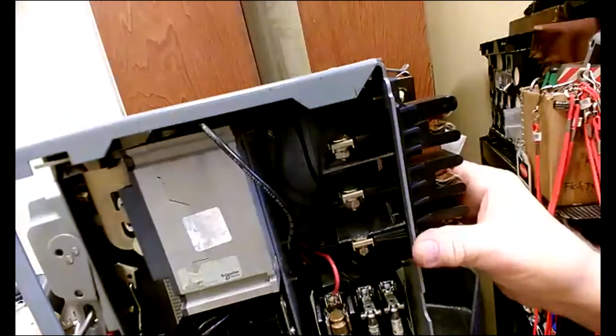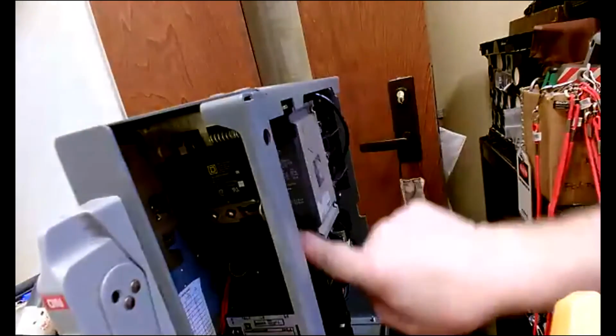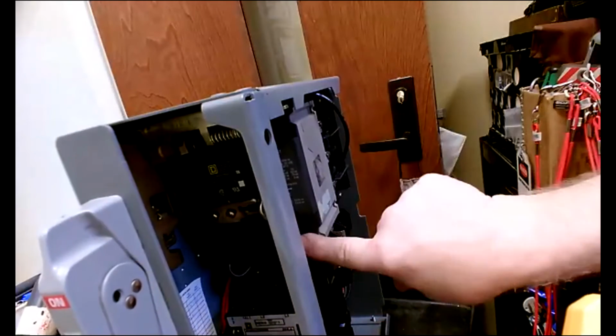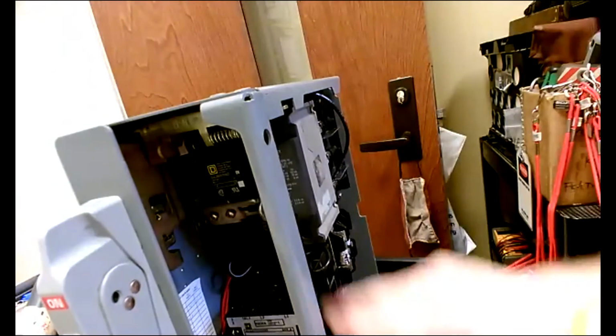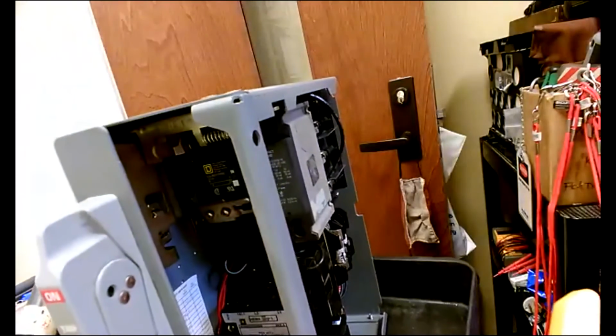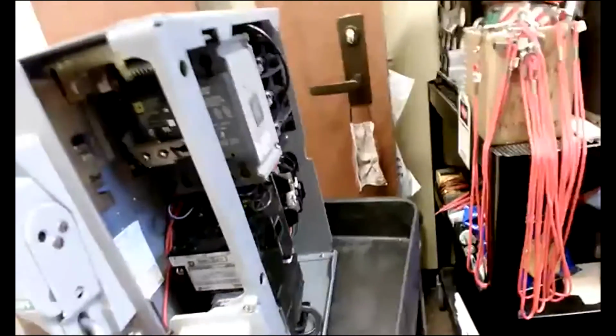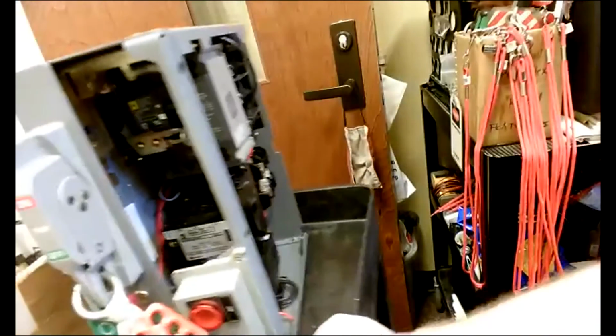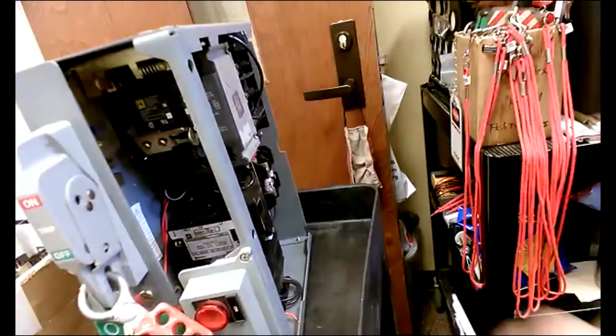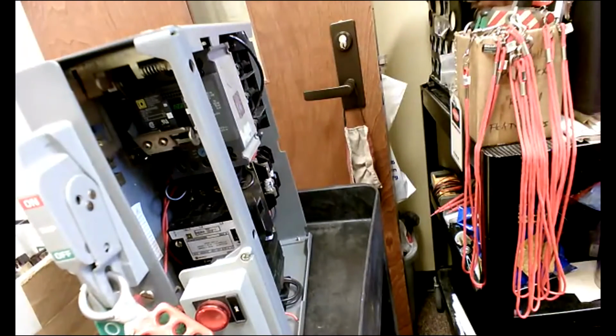Now we know that the main power feeds in from the back bus bars here, from here where it plugs into a wall structure through the breaker panel, so to the breaker. So if the breaker's dead, we know the rest of it's dead. Everything else is downstream, here in this motor control, okay? So we saw that was dead, and then our third step is this. Now it may seem redundant, but just bear with me here.